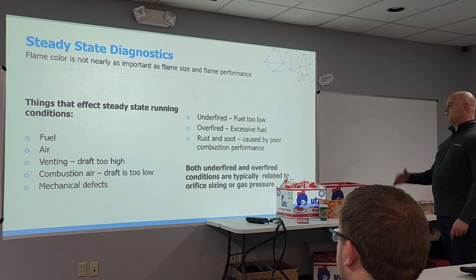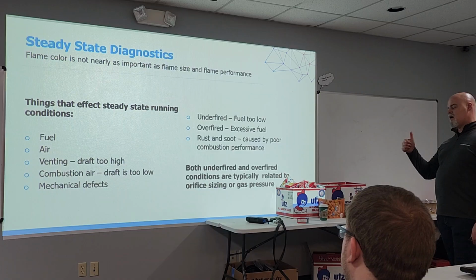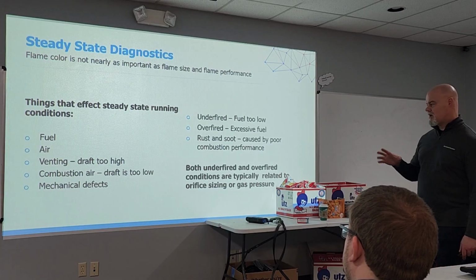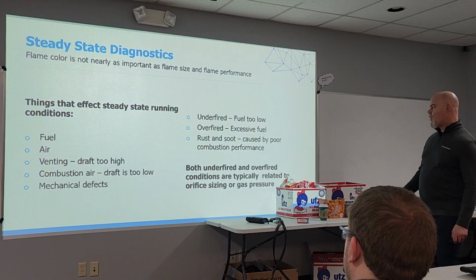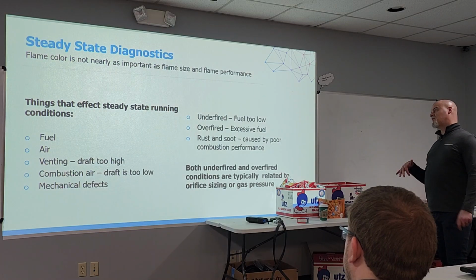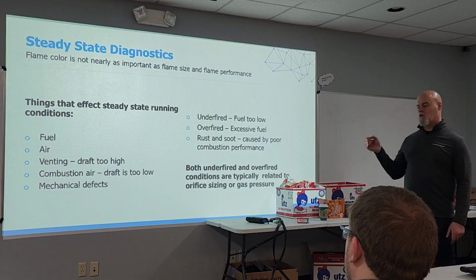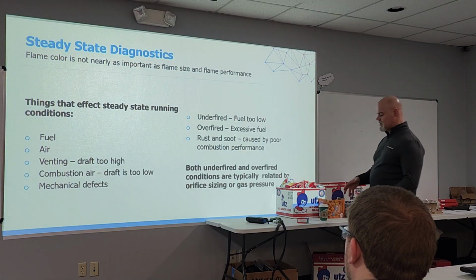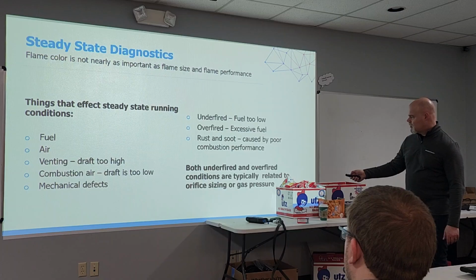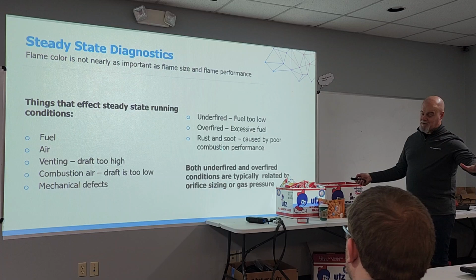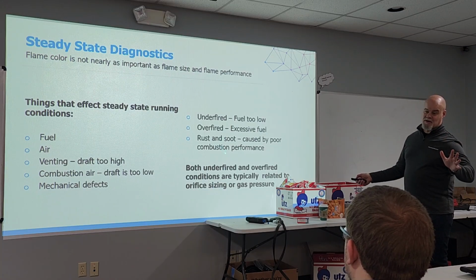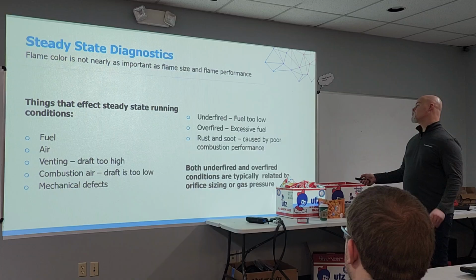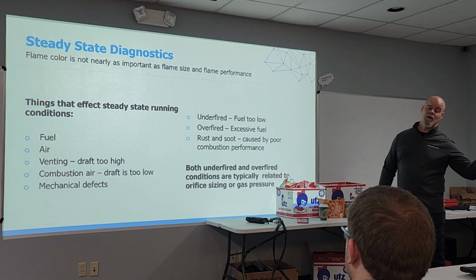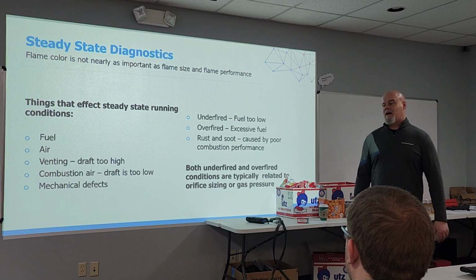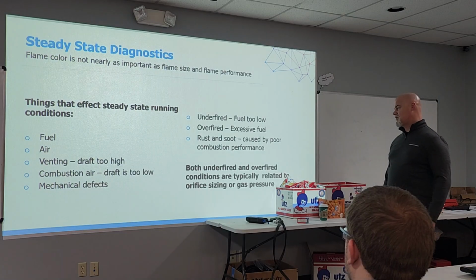Things affecting steady state, again five minutes or greater runtime: fuel, air, venting where draft is too high, combustion air where draft is too low, and mechanical defects. Underfired means fuel too low; overfired means excessive fuel. Rust and soot are caused by poor combustion performance. All roads lead back here. Either you didn't do the maintenance you're supposed to do, which is probably not the case given this crowd, or the previous contractor screwed it up, or the customer didn't call either one of you out to do maintenance, and it went for a while, and that lack of maintenance caused mechanical defects.